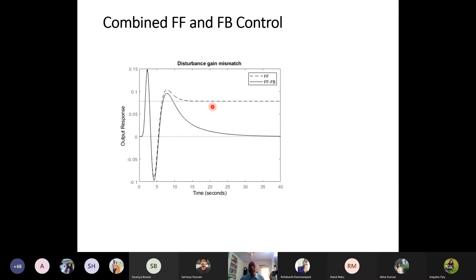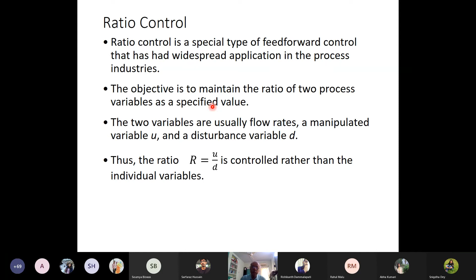Normally in a ratio control, we maintain the ratio of two process variables at a specified value. And this ratio of the two process variables is normally of the flow rates. So we maintain one flow rate in ratio to the other flow rate. When we manipulate one flow rate, that is the manipulated variable, and the flow rate I'm putting in ratio with is the disturbance flow rate. And the ratio R equal to U by D is controlled rather than the individual variable.